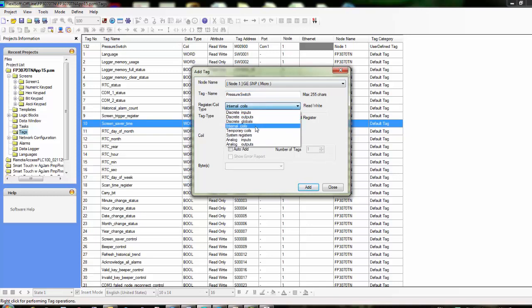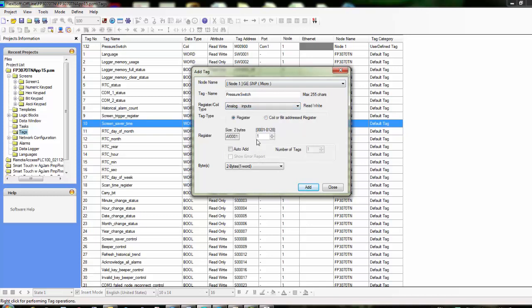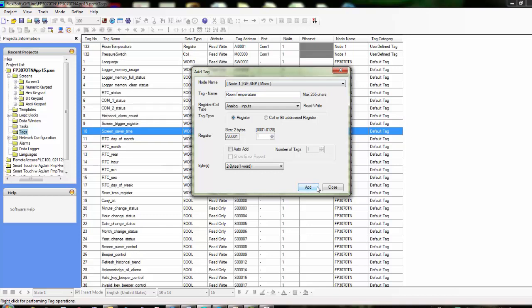You can write to this register and also read that register, and this goes for all these different tag variable types. If you need to read in analog inputs, you can do that. It's going to be a two-byte, one-word variable. This particular PLC has up to 128 analog inputs that it could possibly have. This could be something like temperature—it could be room temperature or whatever that analog input would be on the GE product. We just click Add, and it adds that in.